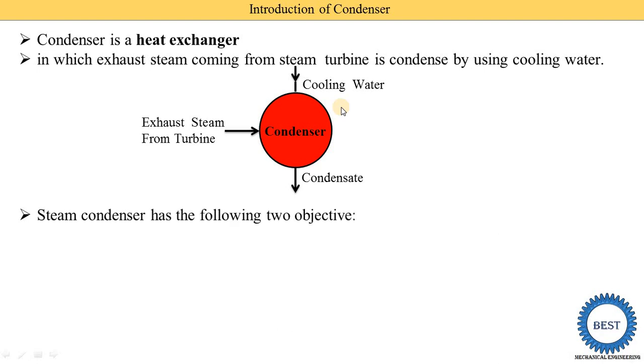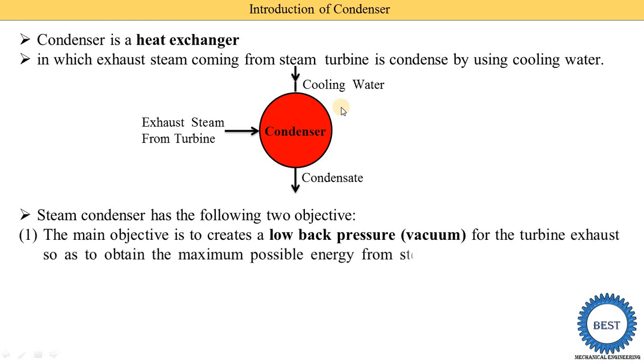Now we understand the objectives of steam condensers. There are two main objectives. The first objective is to create low back pressure — meaning vacuum — for the turbine exhaust, so as to obtain the maximum possible energy from the steam and thus to secure high efficiency. In a turbine there is some exhaust pressure. If we reduce this exhaust pressure from atmosphere pressure down to vacuum pressure, we are able to achieve more work. By using the condenser we can maximize the work done from the turbine.